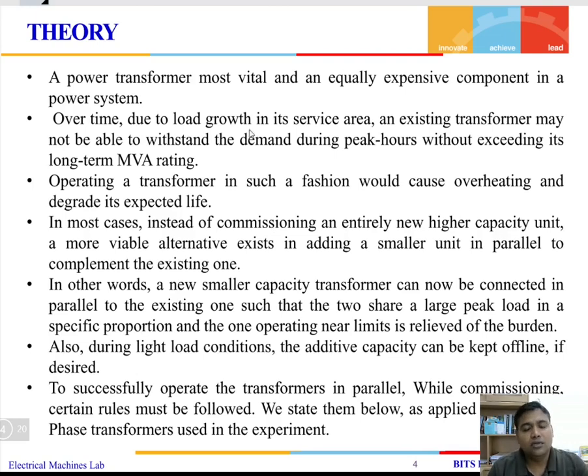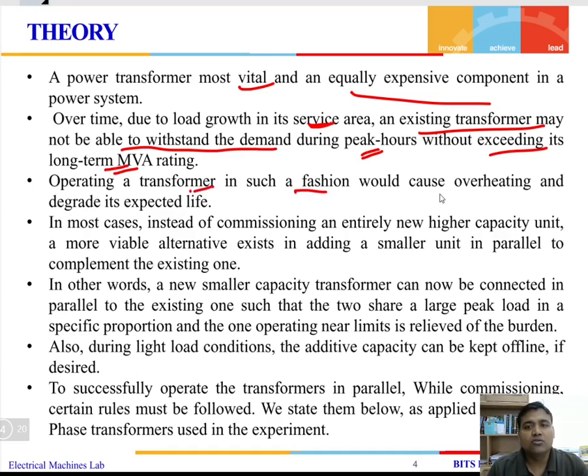We know in theory that the transformer is the most vital and equally expensive equipment in a power system, and as a result of the load growth in the service area, the demand for power is increasing and the existing transformer may not be able to withstand the demand. As the demand increases, only one transformer may not be sufficient to provide the power during the peak hours without exceeding its long-term MVA rating. So we need to increase the MVA rating of the transformer to meet the power demand. Operating a transformer in such a fashion would cause overheating and degrade its expected life. So if you are using a single transformer and the power demand has increased, then over time the transformer will heat up and its life will decrease.